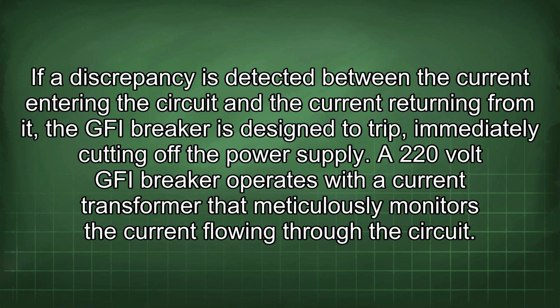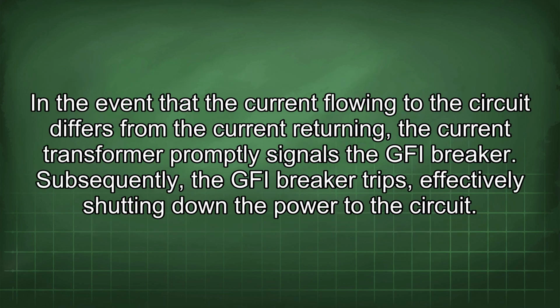A 220-volt GFI breaker operates with a current transformer that meticulously monitors the current flowing through the circuit. In the event that the current flowing to the circuit differs from the current returning, the current transformer promptly signals the GFI breaker. Subsequently, the GFI breaker trips, effectively shutting down the power to the circuit.